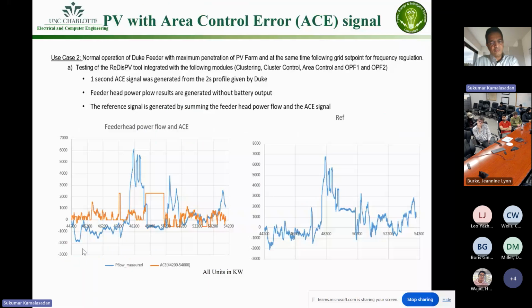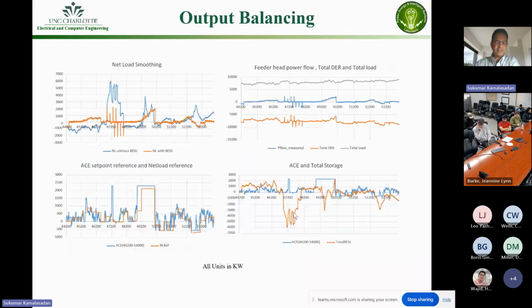One of the use cases Duke wants is to support a frequency signal coming from the transmission side, in the form of an ACE signal that is given to us, and see whether we can honor that signal. We mapped it along with the variable PV or variable DER in the system, and looked at that as a reference signal. So the goal is to track the ACE signal while also making sure we balance the output from the PV farm.